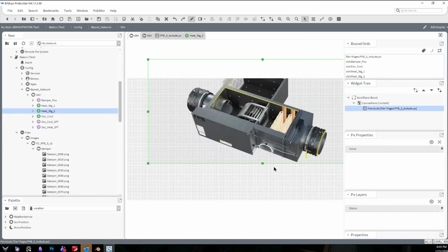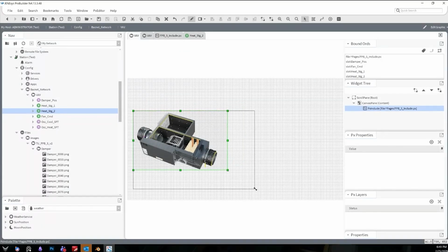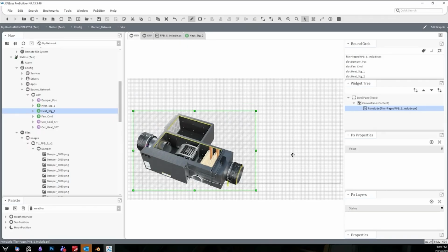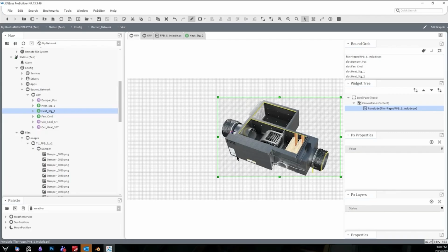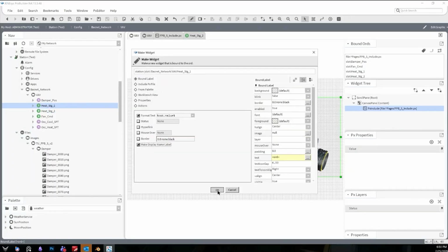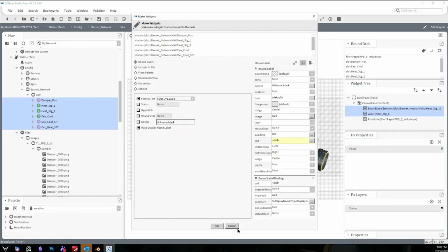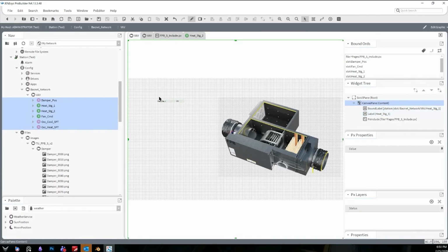And I think people should be using PX includes quite a bit, especially if you're not using reflow or some other front end add-on for Niagara to make Niagara more palatable and more modern. And if you're messing around with PXs, you should be making a library of reusable PX widgets for your point name / point value. It can be as simple as what a point looks like when you drag this in here: you do your bound label with your out dot value and your display name. Typically, make that a PX include, cut that, create a new file, paste that in there, and then you can grab all your read-only points or all your writable points and drag them all in here. Pick that PX file, and you're done.